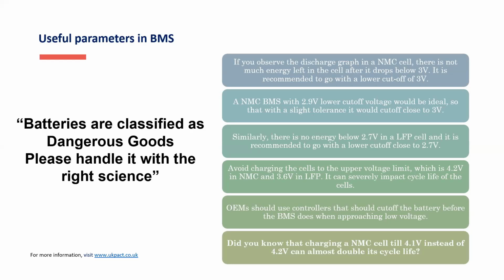Take a BMS which cuts off at 2.9 volts, and with tolerance it comes down to something like 3 volts. Similarly, there's no energy below 2.7 volts in LFP. It's highly recommended to cut off as close to 2.7 as possible. Generally, I recommend 2.8; 2.9 is also okay because it has a flat discharge curve.